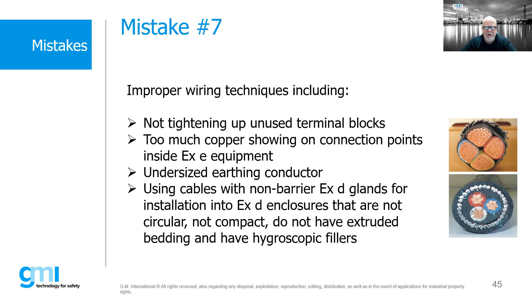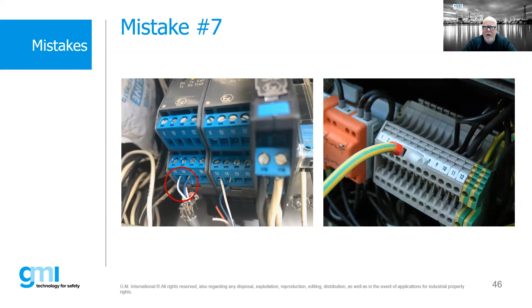Mistake number 7, improper wiring techniques: not tightening unused terminal blocks, too much copper showing inside EXE equipment, undersized earthing conductor, using cables with a non-barrier EXD gland for installation into EXD enclosures that are not circular, etc. We have to be aware of these types of things. As Paulo mentioned, this is all stuff we teach in our various courses, and much of this information is in 60079-14. Here are some other examples of installations with improper wiring.